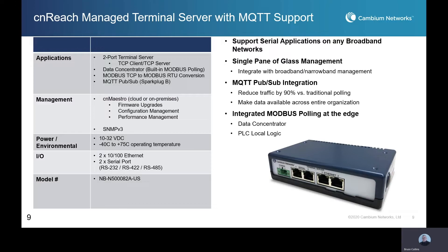A subset of that is our managed terminal server, also managed with CN Maestro. This device allows you to add serial connectivity to any broadband connection — using one of those Ethernet ports to connect into your broadband point, whether it's a switch or directly to the radio, and then provides two serial ports where you can do things like Modbus polling at the edge, MQTT publish/subscribe integration, or simply add console access or serial port access to a broadband network. For example, customers can add this terminal server to achieve serial connectivity into the CLI or out-of-band management port on a microwave link or a remote switch.